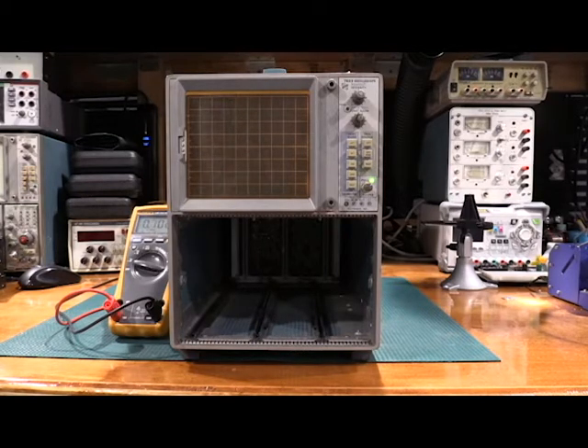That was something I was pretty sure of because the pictures on the listing had the graticule lights on, had the power supply on, so I knew the power supply was at least turning on, but there doesn't seem to be any shorts. Now, the listing did say there was no high voltage, or there was no trace. Without any of the plugins in, the waveforms aren't right, so it won't develop a trace on the screen. So what I'm going to do now is, because I don't want to fry out any plugins and I don't know what the power supply health is, I'm going to do voltage checks on the power supply, check all the rails, make sure they're all in spec, and then I will take a couple of my spare plugins. We'll see if we can't at least get a trace.